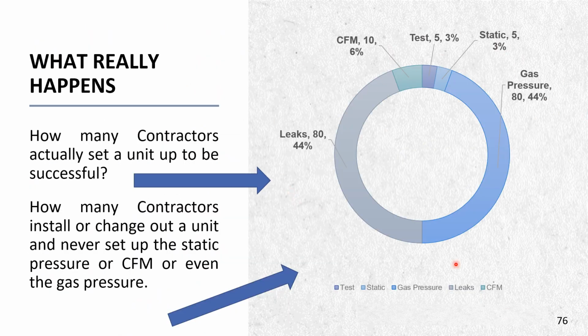Now, here's one thing I want to show you: most people have been doing it for so long, they just think it's the same as any other unit. They install it the same way, and they turn the unit on. They call for heat. It comes on. They walk away. They do not set the static pressure. They do not set the CFMs up. And a lot of times they won't even set the gas pressure. So looking at this, there's probably 3% of all contractors actually test the unit, and 3% set up the static pressure. Probably 6% only check CFMs.